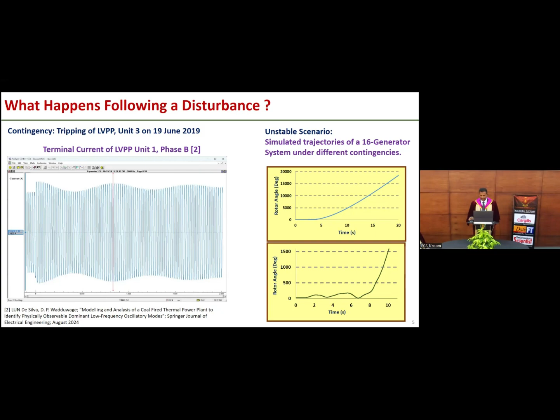In real situations, a disturbance can trigger a number of cascading events, and the system can come into a total failure. So I have two cases. The first case here is the 2016 event in our power system 10 years ago, where the system collapse was initiated from a line to ground fault in the 132 kV line, and it triggered cascading failures, and eventually the system led into a total outage.